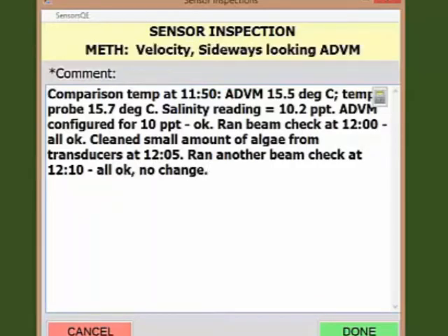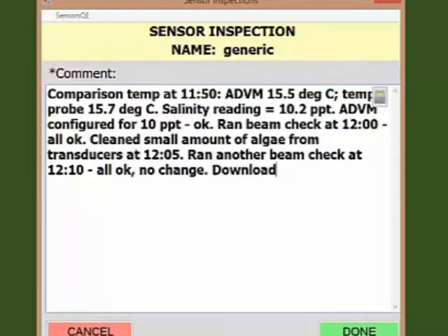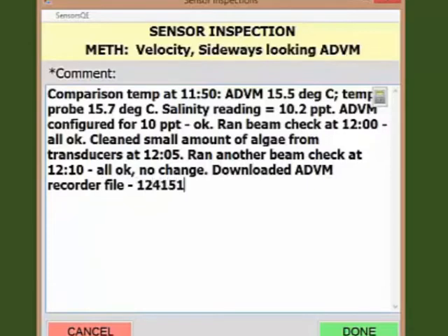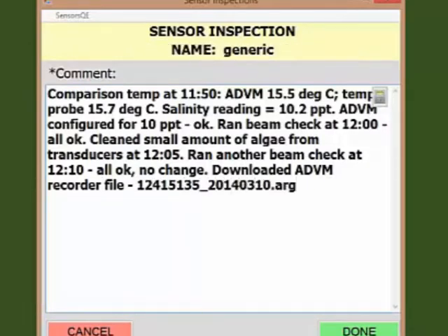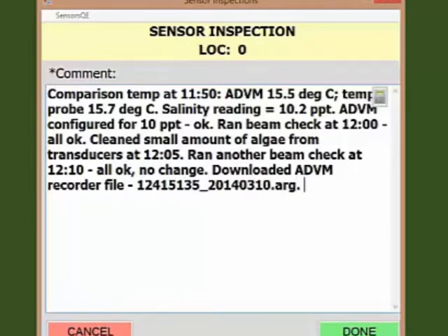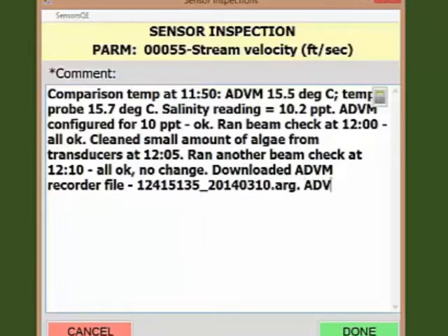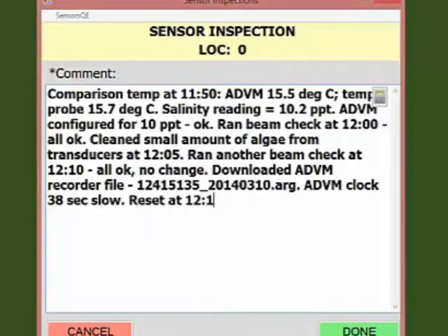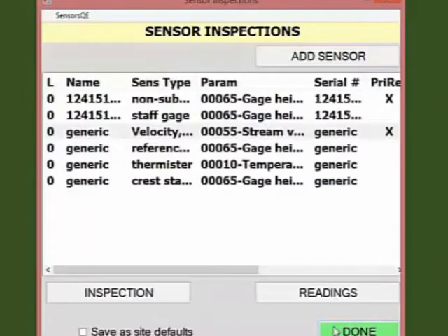Next, whether the internal ADVM recorder was downloaded and document the file name. I'm going to write: downloaded ADVM recorder file, 12415135_date.arg, which is the name of the file. Next, what the clock reading was on the ADVM and whether it needed to be adjusted, and if so, by how much. I'm going to write: ADVM clock, 38 seconds slow, reset at 12.15.20. Click Done to return to the sensor inspections table.